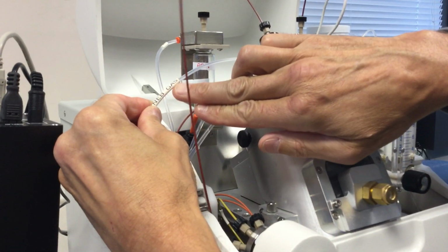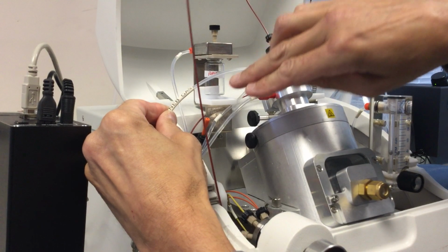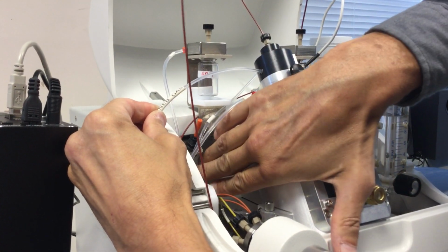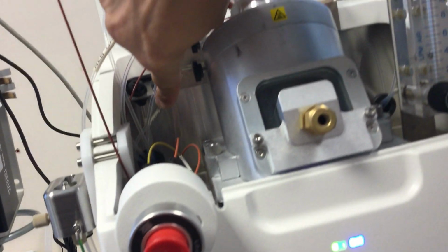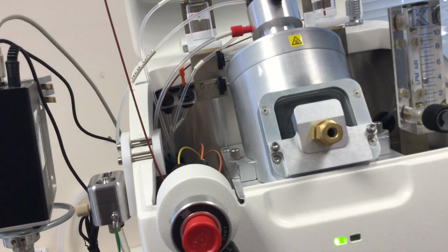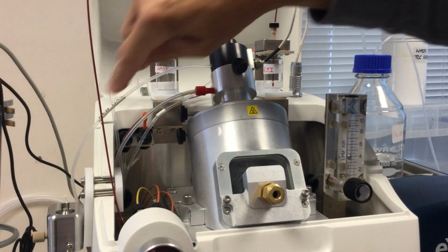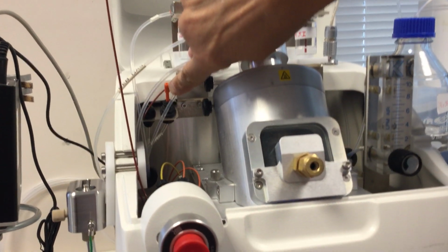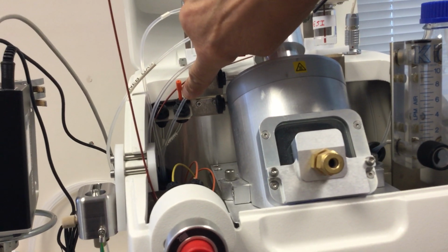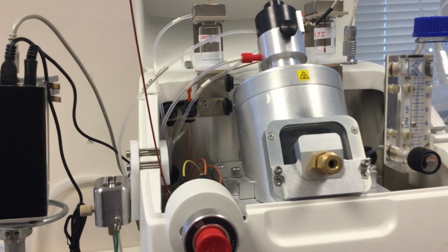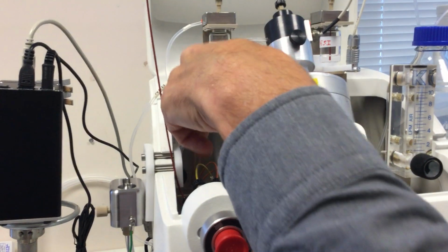It's got nebulizer gas on it. Yep. And ordinarily, your nebulizer gas is plugged into there. There's a label on there as well. Yep. So if this was a regular ESI source, that line would be plugged into where that orange plug is now. Yep. But we need a bit more pressure than we can achieve from that line there.